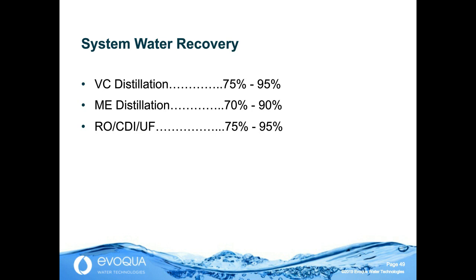In a typical RO CDI UF, 75% was popular for decades because no one was really too worried about water recovery. Today, with enhanced water recovery, that's typically an additional RO working on the main RO waste. That recovery can be as high as 95%. So all can be relatively low, all can be very high total water recovery.